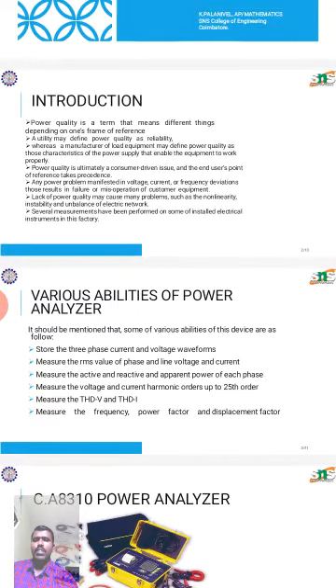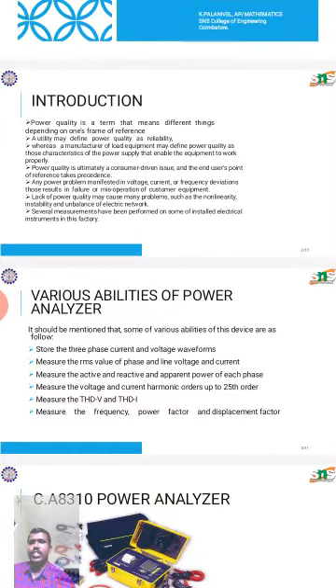Therefore, the following definition of a power quality problem is sometimes used: any power problem manifested in voltage, current, or frequency deviations that results in failure or misoperation of customer equipment. It defines power quality as the concept of powering and grounding sensitive electronic equipment in a manner suitable for the equipment.